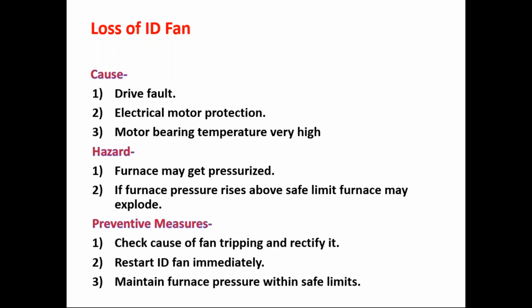Now the next operational issue may be loss of ID fan. Why can this loss occur? The causes or reasons may be a drive fault, an electrical motor protection trip, or a very high motor bearing temperature. So all these can be causes. And what are the hazards? The furnace may get pressurized because the ID fan is off. If furnace pressure rises beyond the safe limit, obviously the furnace may explode. So these are the different hazards, that is, pressure increase due to this loss of ID fan.